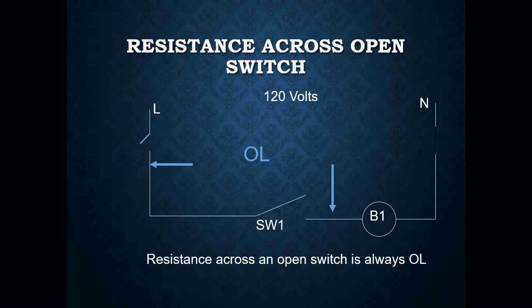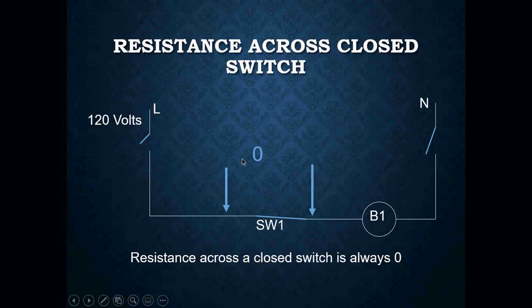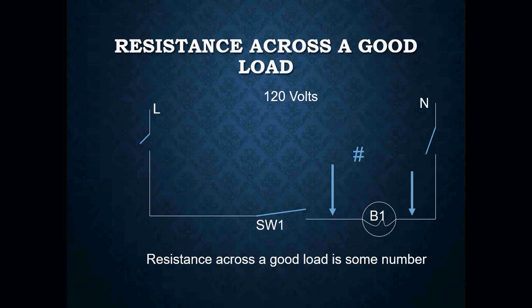Okay, so here we are, resistance across an open switch. I'm going across before and after my switch number 1 here. We will see that it's open. Our meter will read OL, open load, as I like to think about it. Okay, when I go across a closed switch, I'm going to read 0. It's telling me that between point A and point B, I have a complete path. It's 0, not picking up any sort of resistance. Remember, a switch has no resistance to begin with, so you should have 0 resistance across a closed switch.